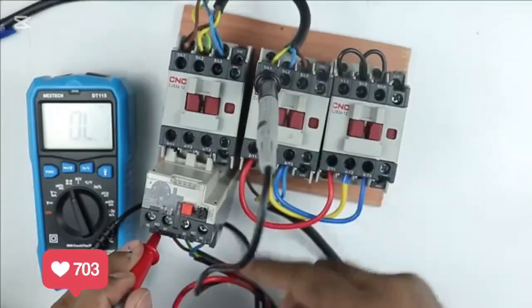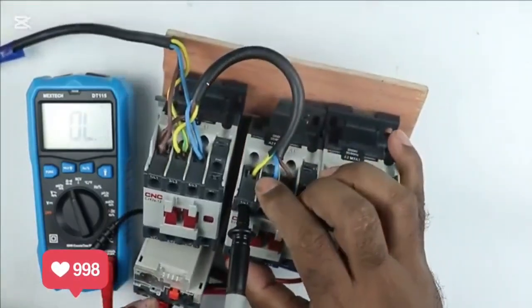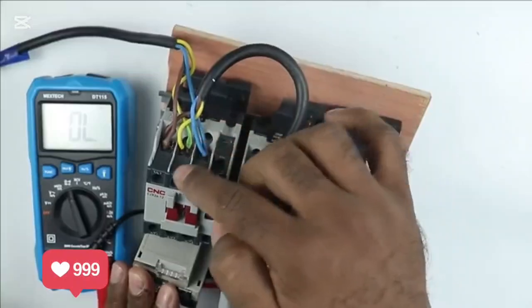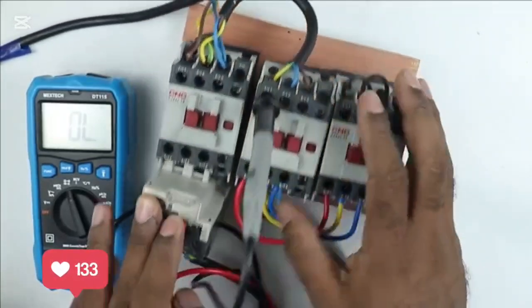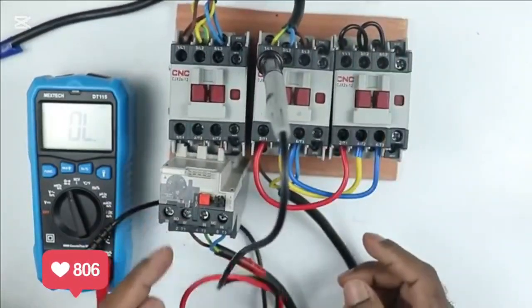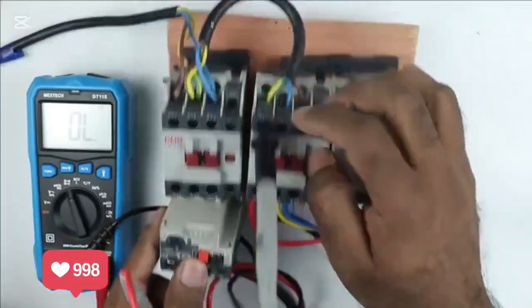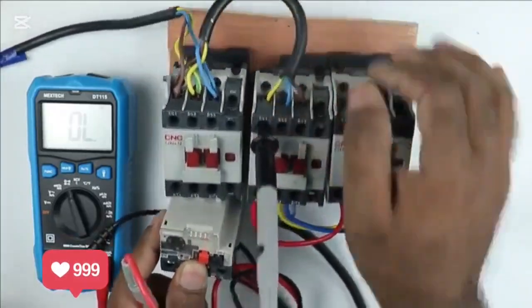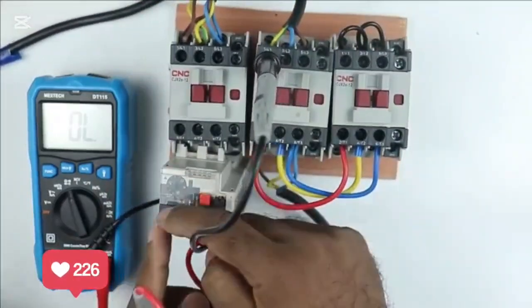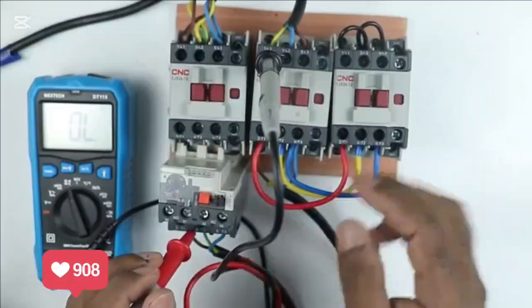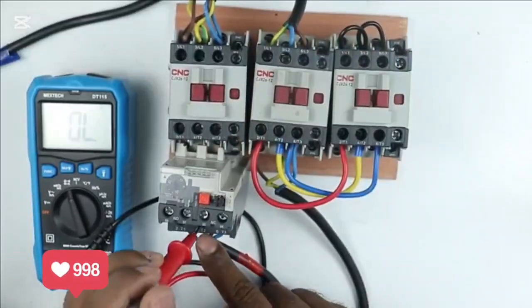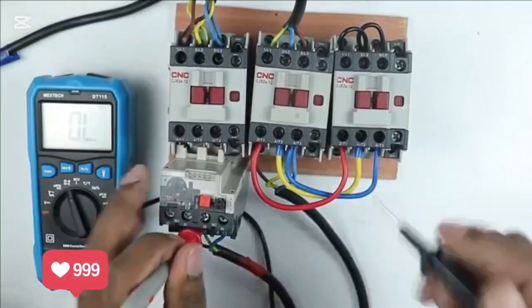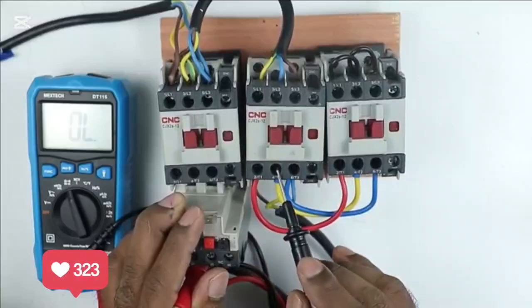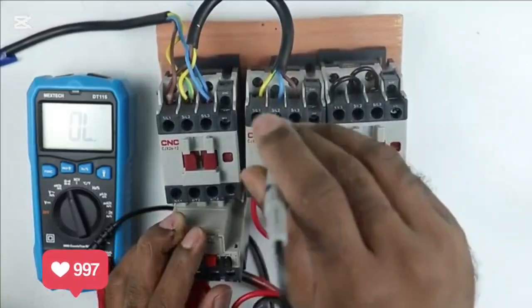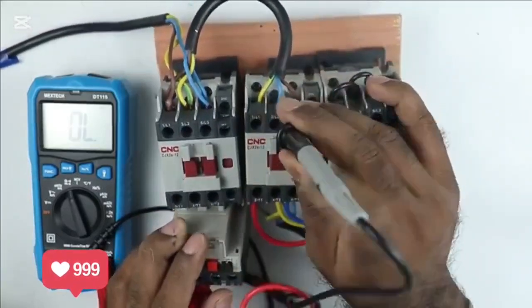This means from here power supply will come through this wire, and through yellow wire it will move further and connect here to yellow wire. You can see at this point R phase wire is connected, and at this point Y phase wire is connected. This means to one winding two phase power supply is connected. So this connection is right. Let's check for second terminal. I connected probe on this terminal, I mean at Y wire. Output of this is connected at this point. So we will get output at this point.